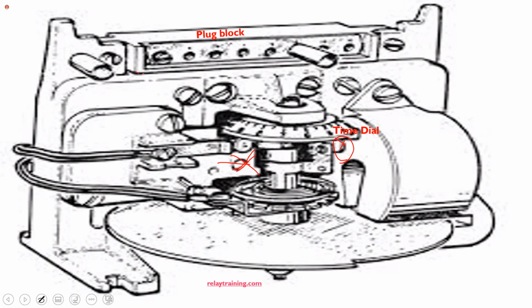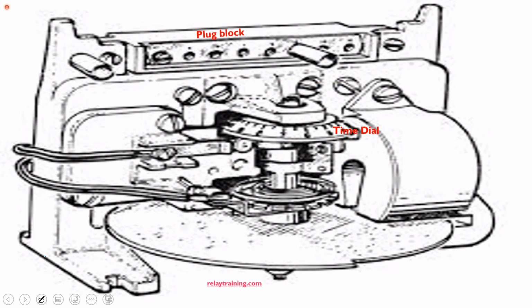Lastly, up here, I have it highlighted as the plug block. We call it plug block because what we have here, that's your plug. And what you have here are some holes or openings. Each of those openings has a number written on it, and that number represents the setting current for the relay. To select one of those numbers, you simply remove the plug and insert it into one of those openings. So you'll take your plug and put it over here.